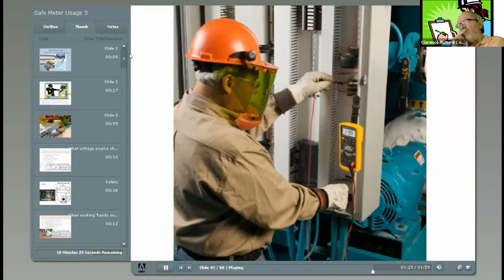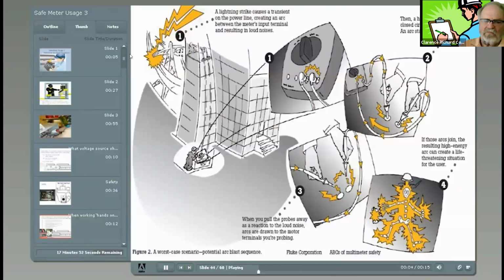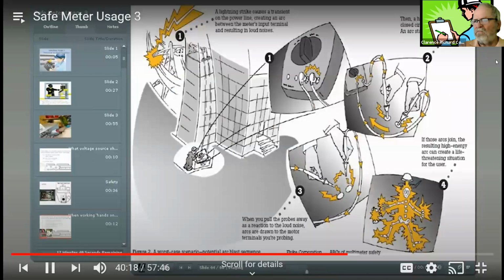Use the 3-point test method, especially when checking to see if a circuit is dead. First, test a known live circuit. Second, test the target circuit. Third, test the live circuit again. This verifies that your meter worked properly before and after the measurement. Use the old electrician's trick of keeping one hand in your pocket. This lessens the chance of a closed circuit across your chest and through your heart. Let's take a look at a worst-case scenario in which a technician is performing measurements on a live 3-phase motor control circuit using a meter without the necessary safety precautions.